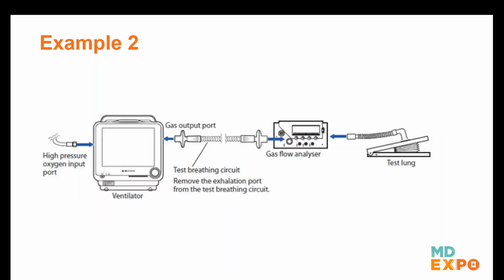Here's another example, another manufacturer. And they use line drawing, but they show you their ventilator. Again, they show you the tubing circuit, and they show you an analyzer and a test lung. What they fail to do here is give you any guidance on which ports on the analyzer to use. So of course, there's going to be additional information in the manual that tells you things, but just from this drawing, you really can't tell.